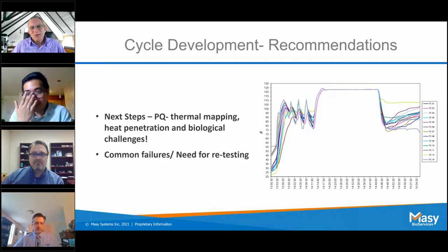Yeah, and one of the earlier pictures of the sterilizer had an observation that it should be papered down so that any moisture or water can actually run down through it. If it's paper down, plastic down, it'll pool up in there, and that's a no-no. That's one. The other is, I absolutely have to emphasize what Sylvan mentioned, which is to be calibrated properly prior to doing the testing. I've had too many failures where it's been calibrated, checked, yes, you do the IQ, yes, it's been calibrated, and you find the results are totally skewed off, and that's devastating, as in any validation effort.